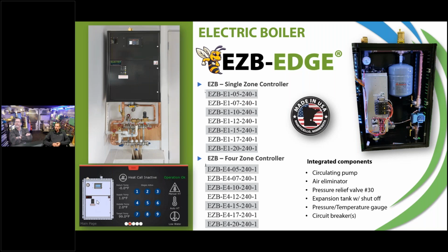The EZB-Edge is definitely a fun boiler. Being able to set priorities for zones and designate which zone has priority is pretty cool. It comes in two versions, the 4-zone and the single zone controller. If you're using external zoning controls like a Taco relay, you can go with the single zone controller—we just need an end switch to come back saying there's a call for heat. The 4-zone controller lets you do a combination of zone valves or circulators, so if your job has a mix, you don't need two separate relays, which is pretty wild.